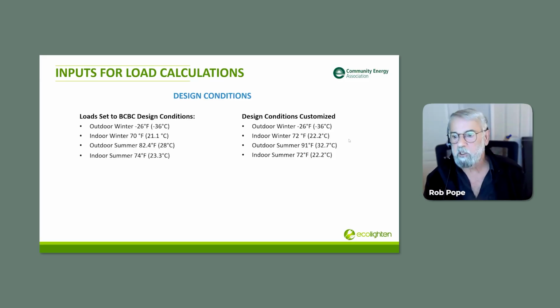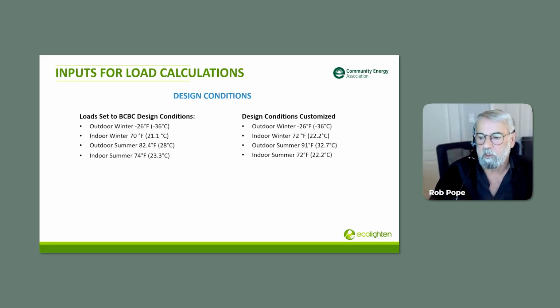So let's say we did that. We keep the outdoor winter condition the same since it doesn't make much difference. But the indoor winter temperature does matter. Maybe they want 72 degrees, or 22.2 Celsius, instead of 70, the standard approach. The outdoor summer condition, as we saw in the actual Environment Canada data, was much higher than the BC code minimum. So let's bump that up to create resilience in the system for a changing, warming climate, to 32.7, 91 degrees.